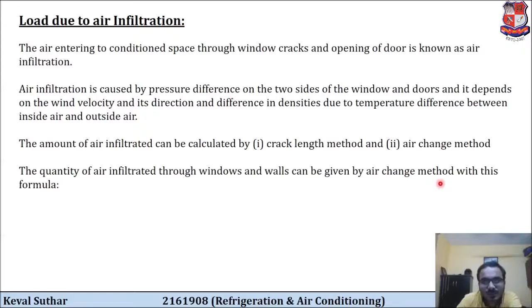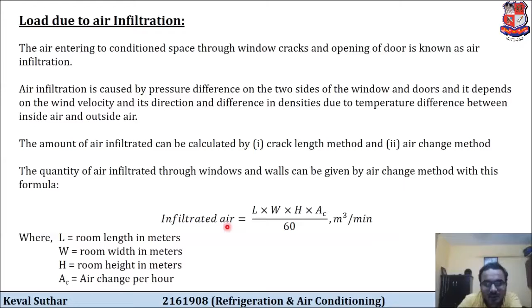So the quantity of air infiltrated through windows and walls can be given by the air change method with this formula. The formula is infiltrated air is equal to L W H AC divided by 60 meter cube per minute, where L is the room length in meters, W is room width in meters, H is the room height in meters, and AC is air change per hour. That will give us the quantity of infiltrated air in meter cube per minute. So this was load due to the air infiltration.